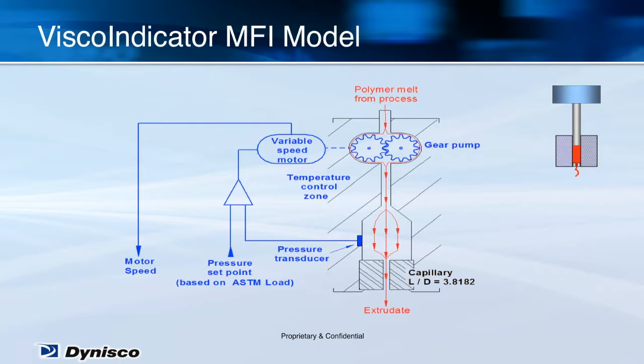In the ASTM mode of operation, the pressure defined by the load in the piston is specified in the ASTM method and created by controlling the gear pump flow rate using data from the pressure transducer. The material flow rate is calculated from the speed of the gear pump. A gear pump is essentially a positive displacement device that pumps the melt at a constant rate, regardless of the resistance to flow. By measuring the gear pump speed required to control pressure at the ASTM set point and knowing the pump flow rate, the visco indicator is able to calculate MFR directly as a function of pump RPM, given that the melt density is known. If you don't know the melt density for your polymer, you can easily measure it using a standard method on a melt flow indexer. This is how a visco indicator duplicates the test result from a melt flow indexer right on the extruder without needing a technician.